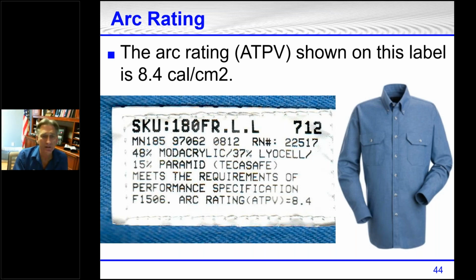If you're familiar with calling them FR clothing, fire resistant clothing, with 70E that term FR was eliminated two or three editions back. It always had to be arc rated, but there was a term used in there for FR, and some clothing manufacturers or laundry services may refer to it still as FR, and that's okay. But it also always has to have an arc rating, either ATPV, arc thermal performance, or energy of break open threshold, E sub BT.